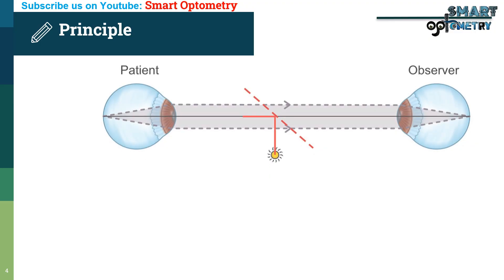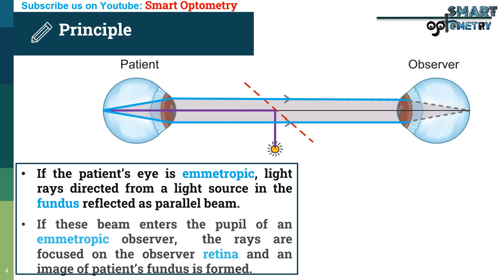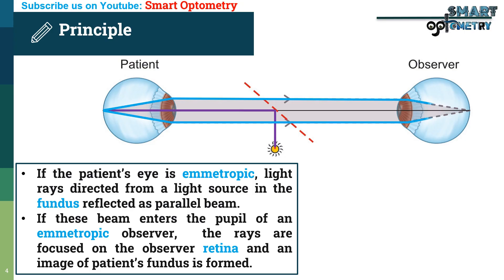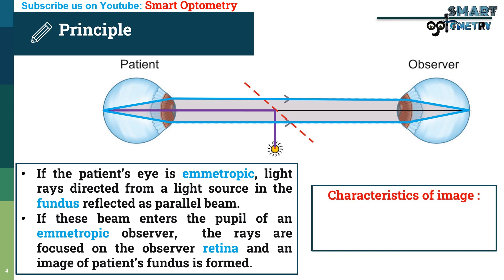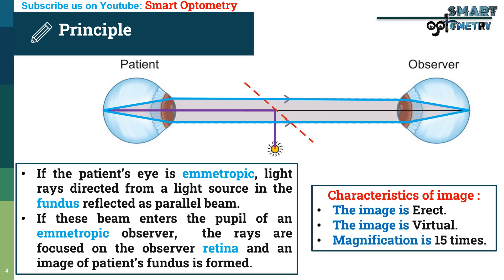Principle of the direct ophthalmoscope: if the patient's eye is emmetropic, then light rays directed from a light source to the fundus are reflected as a parallel beam. If this beam enters the pupil of an emmetropic observer, the rays are focused on the observer's retina and an image of the patient's fundus is formed. The image formed is erect, virtual, and 15 times magnified.